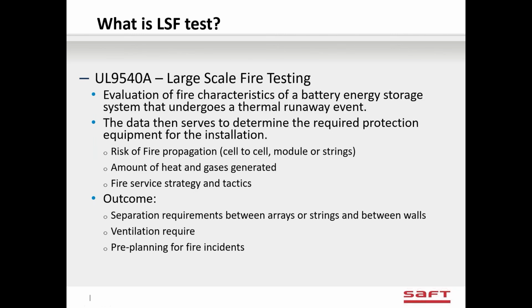So what is large scale fire testing? There's a UL test method called 9540A. It's a large scale fire testing. And the goal of this is to determine what the risk of fire propagation is, cell to cell and module to module, the amount of heat and gases that are generated, and what your fire service strategy and tactics should be for your design of your room. Depending on the outcome, it will determine whether or not you need that 3-foot spacing between your 50 kilowatt hour arrays.